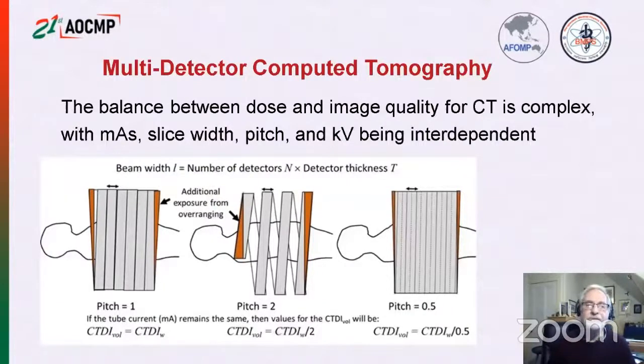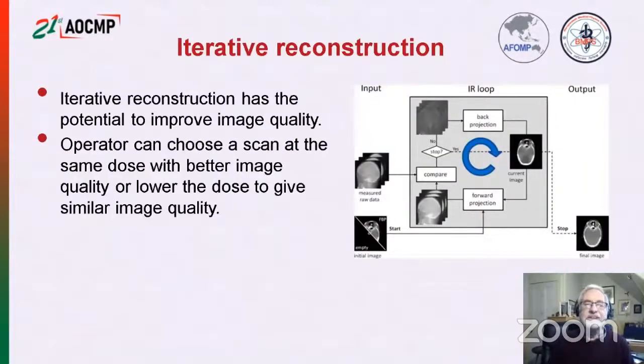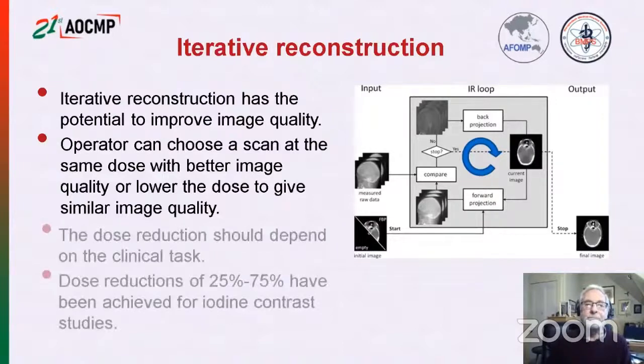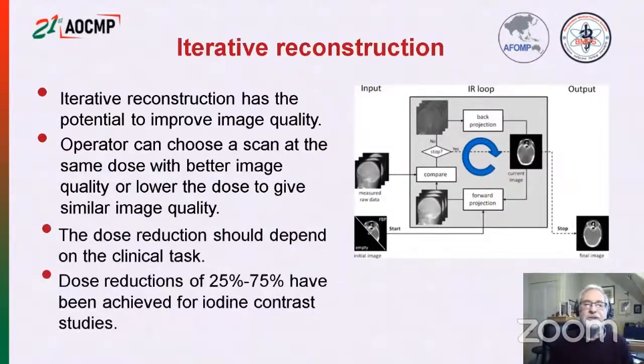And for computed tomography, the balance is between dose, mAs, slice width, pitch, kV. They're all interdependent. Then we've got things like iterative reconstruction to consider, which can improve image quality. So the operator can choose a scan at the same dose with better image quality, or they can lower the dose through the scan parameters to achieve similar image quality to the standard. And the dose reduction should depend on the clinical task, but dose reductions of 25% to 75% have been achieved.